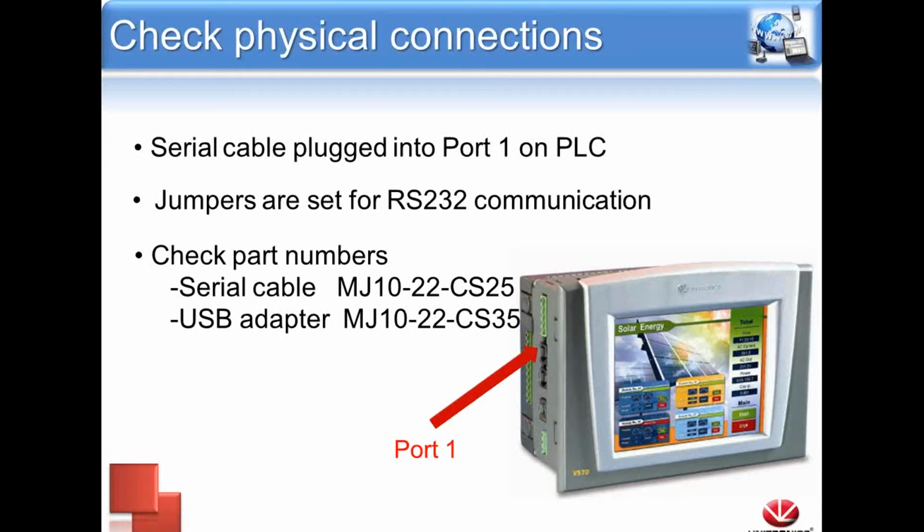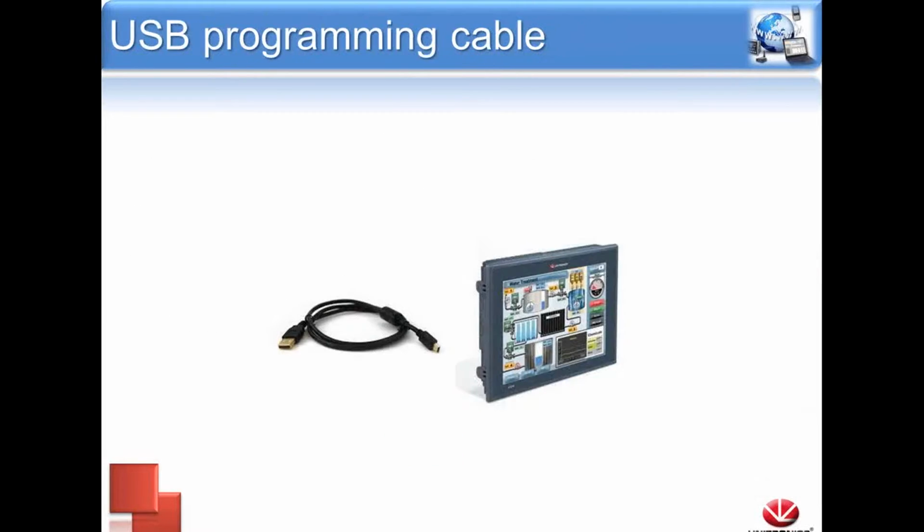We will then confirm the serial cable and USB adapter conform to the part numbers listed. For example, the connector used in modem communications has a different part number and pinout than the connector used in this case. Despite its almost identical appearance, the part number listed on the converter will differ, and if used in lieu of the intended device, will ultimately result in failure.